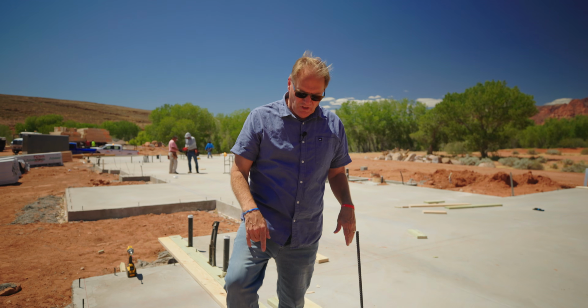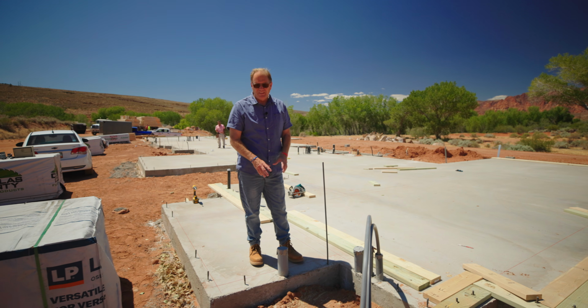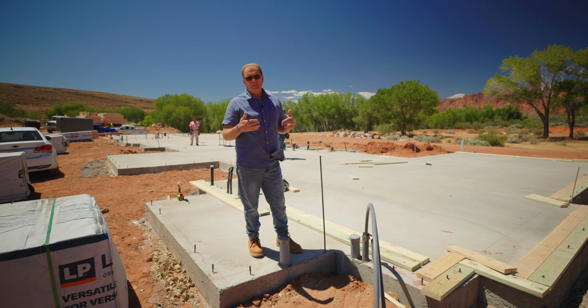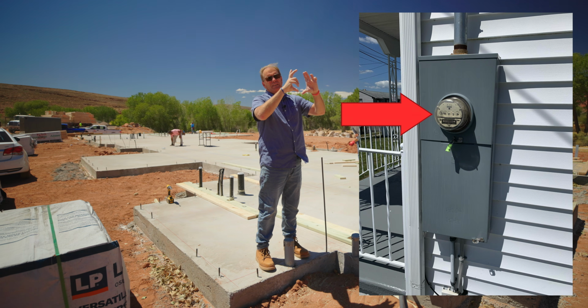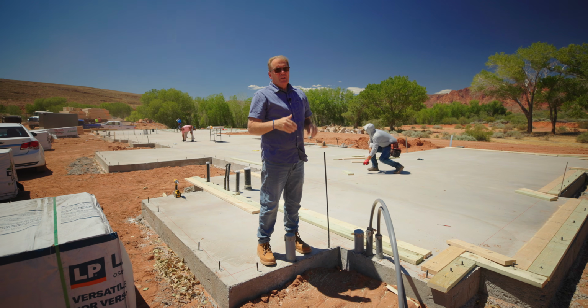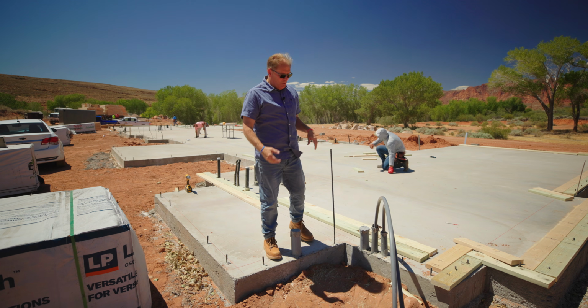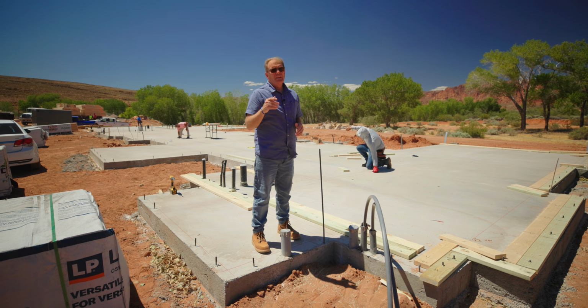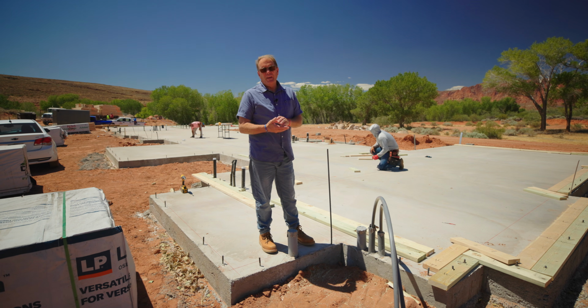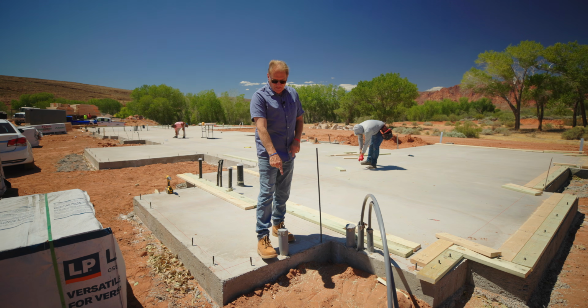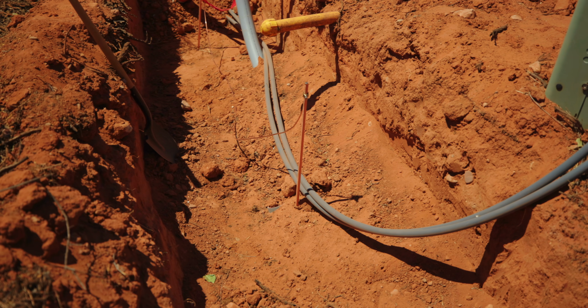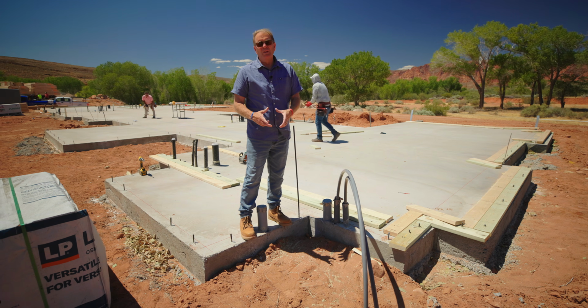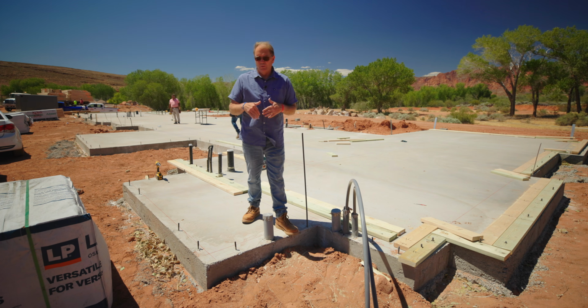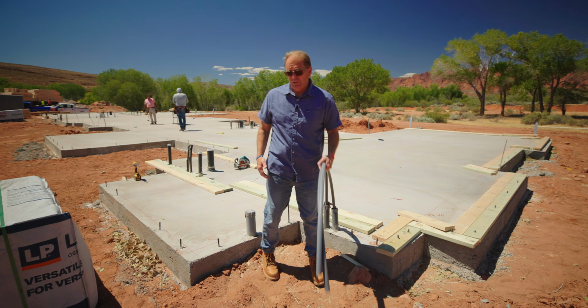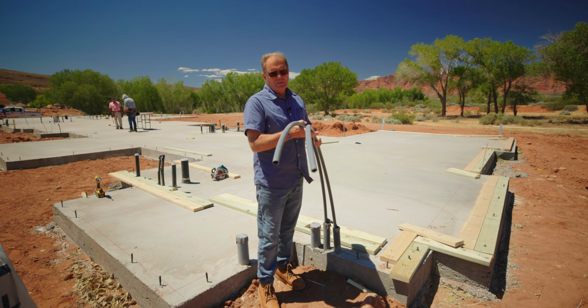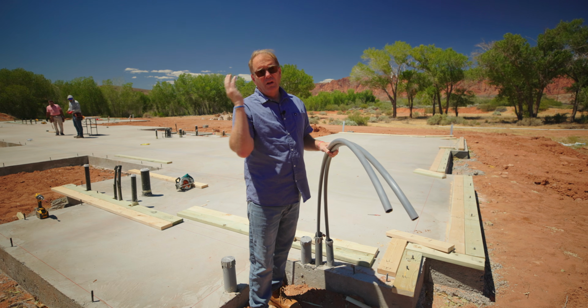Right here we've got a 3-inch conduit coming up through the concrete, and that's going to be our power. We are not going to do a meter panel on the house. A meter panel is where you see that round glass thing moving a little bit when it's drawing power. That's going to be over by the power pole, and I'll explain why in a second. We had a trench go through here, took a picture of that, and had an inspection, which passed. Before the inspection, we ran a conduit, connecting it outside about 3 feet down in the dirt. In that trench we ran a conduit which is going to pull our main power line for the home. We also ran a conduit, which is what you see right here, for cable, digital, low voltage, etc. That's also running out to the power.